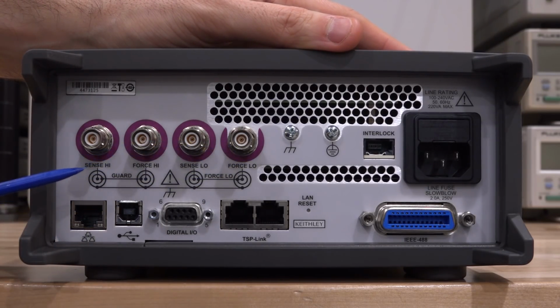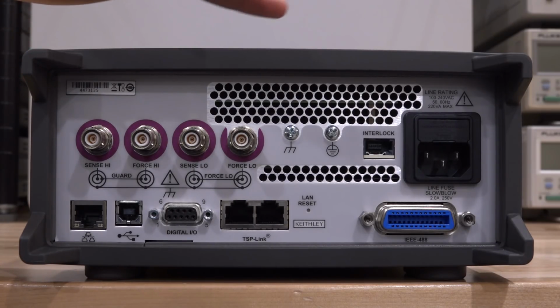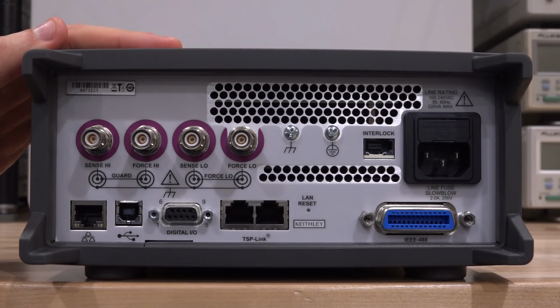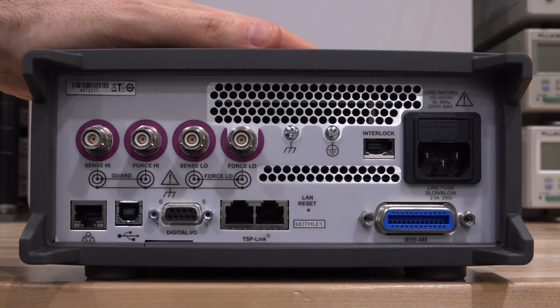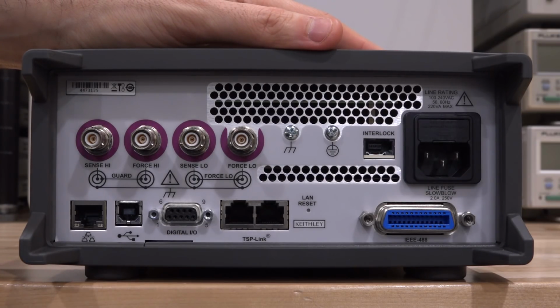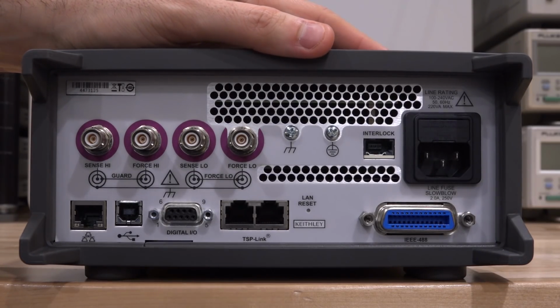Then we have 4 triax connectors in the back. The use of the triax connectors for this instrument is also pretty important, because when you go to 1000 volts, measuring currents in the orders of nanoamps becomes quite difficult, since everything leaks at these high potentials, and these strong electric fields across conductors can cause a leakage current to go through. In order to solve that, you have to have a guard voltage with you to basically stop the flow of electrons across the conductor, and that is done using these triax connectors.